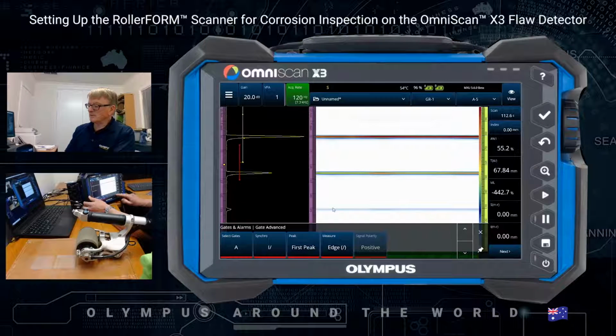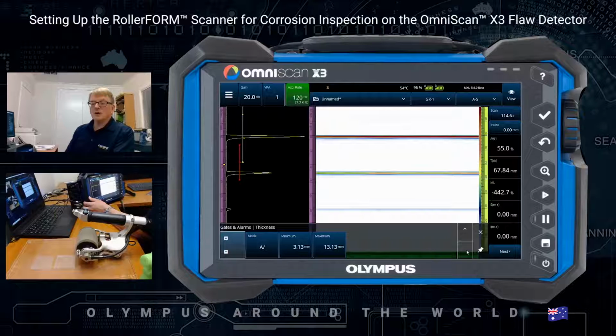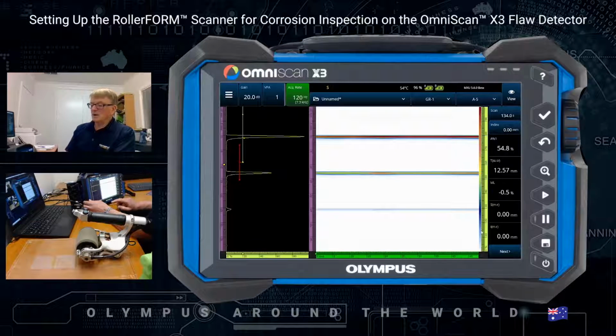If I press the little button and go down one to the next menu, we then select the A-I as the thickness measurement. And now you'll see up on the right hand side where the thickness is, it says T A-I 12.57. Okay, so we've got the right answer. Next thing is to look at sensitivity. So if we notice that the back wall echo is much smaller than the interface echo, that's because of material attenuation.